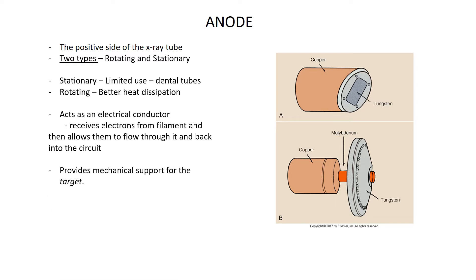The anode also provides mechanical support for the target, which is on the face of the anode where the x-rays are going to be created. The anode also has to be a good thermal conductor, because when you create x-rays, 99.8% of the kinetic energy of the electrons turns into heat.